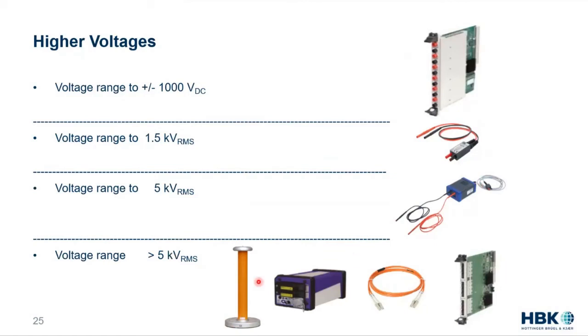We actually have isolated digitizers. So we'll have the voltage divider. We'll have an isolated digitizer sitting in the test cell with the very high voltage. We digitize the signal in the cell, and we put it out over a fiber optic cable. So it's completely noise immune, completely safe for the equipment and the users. Back to the test instrumentation, where we read that fiber optic cable.